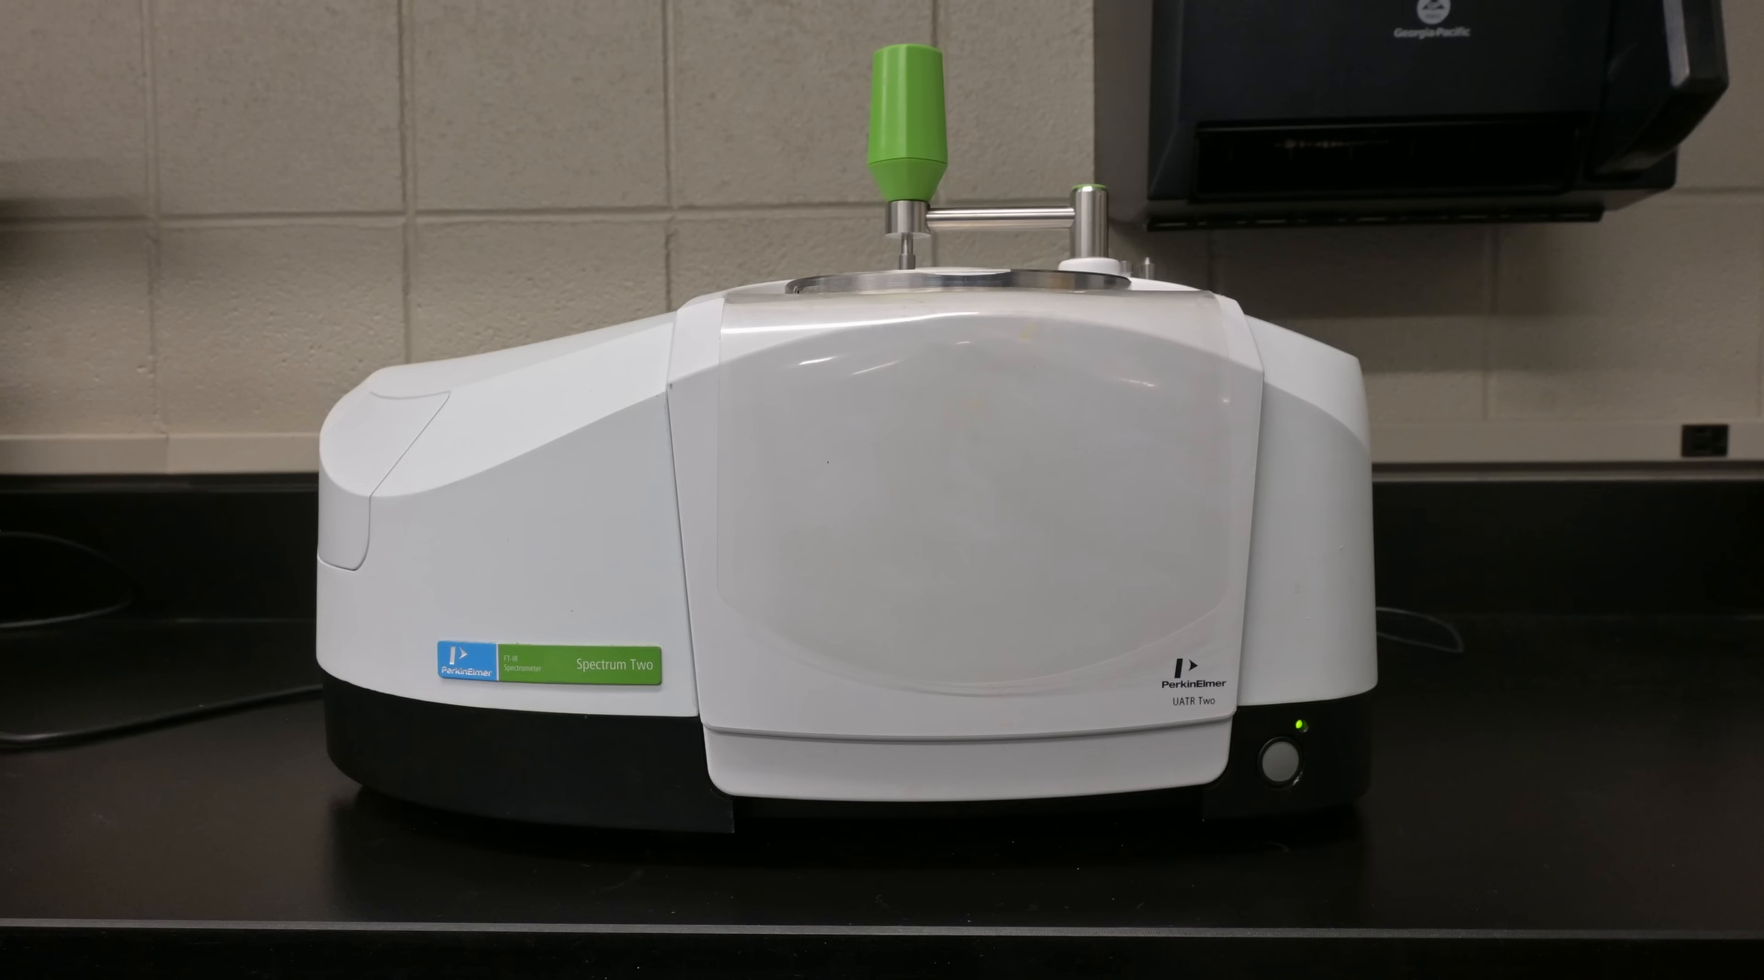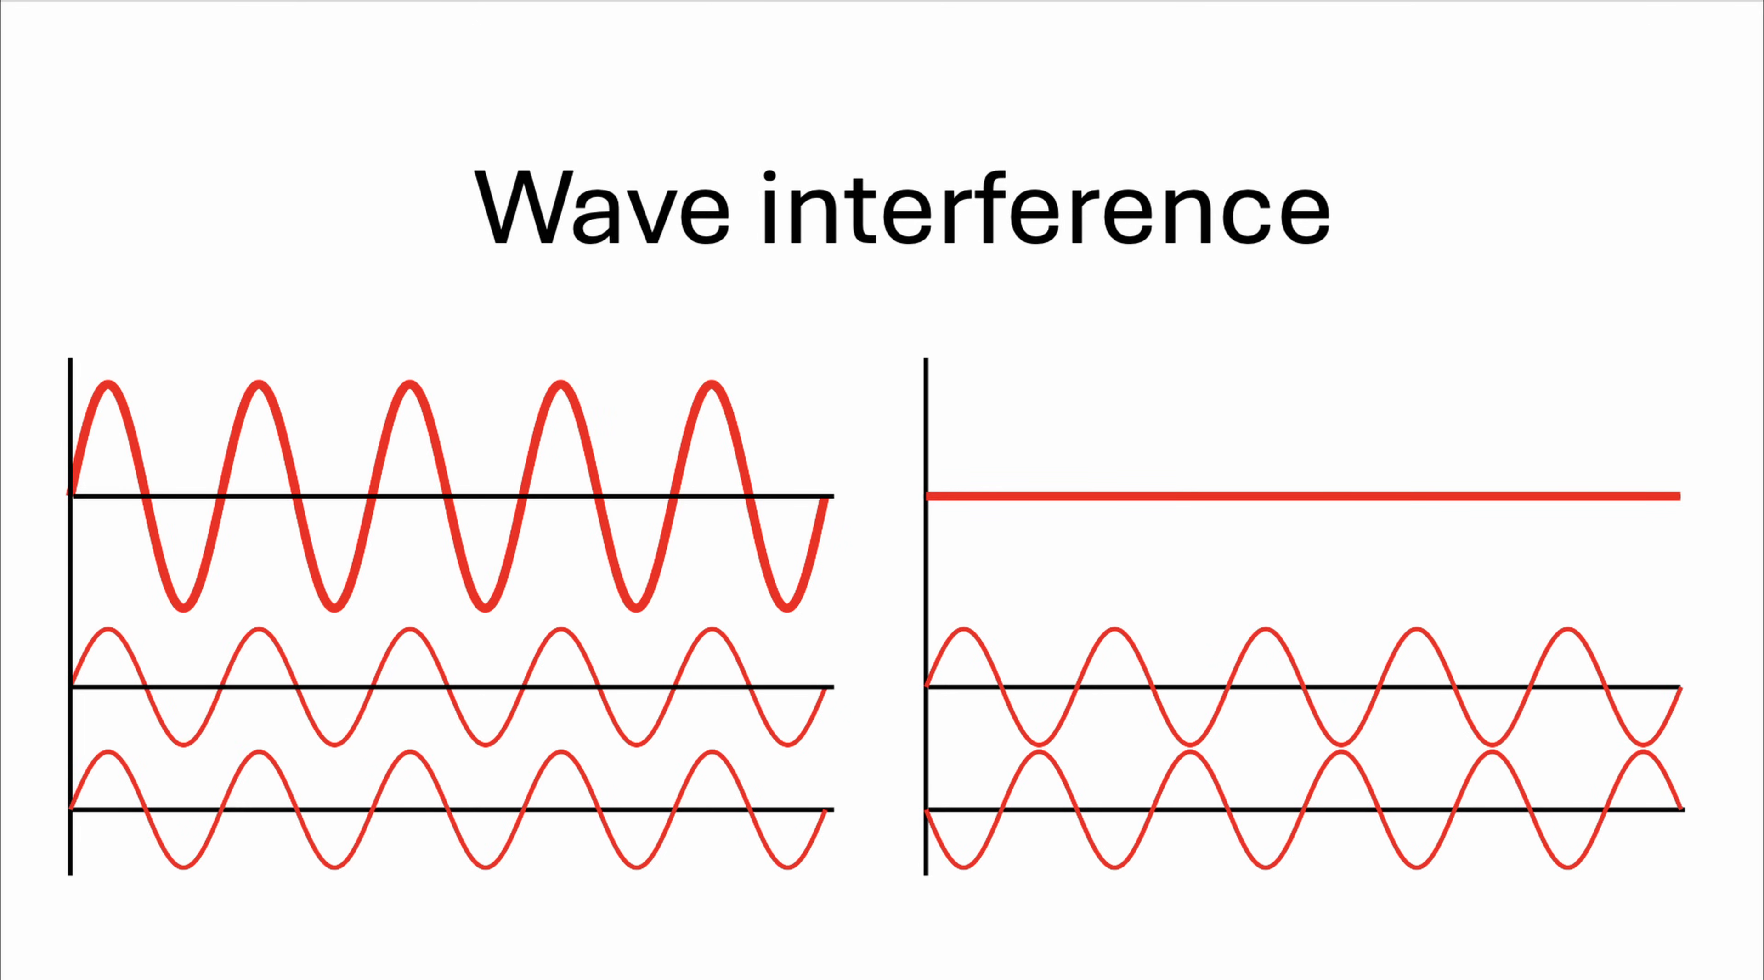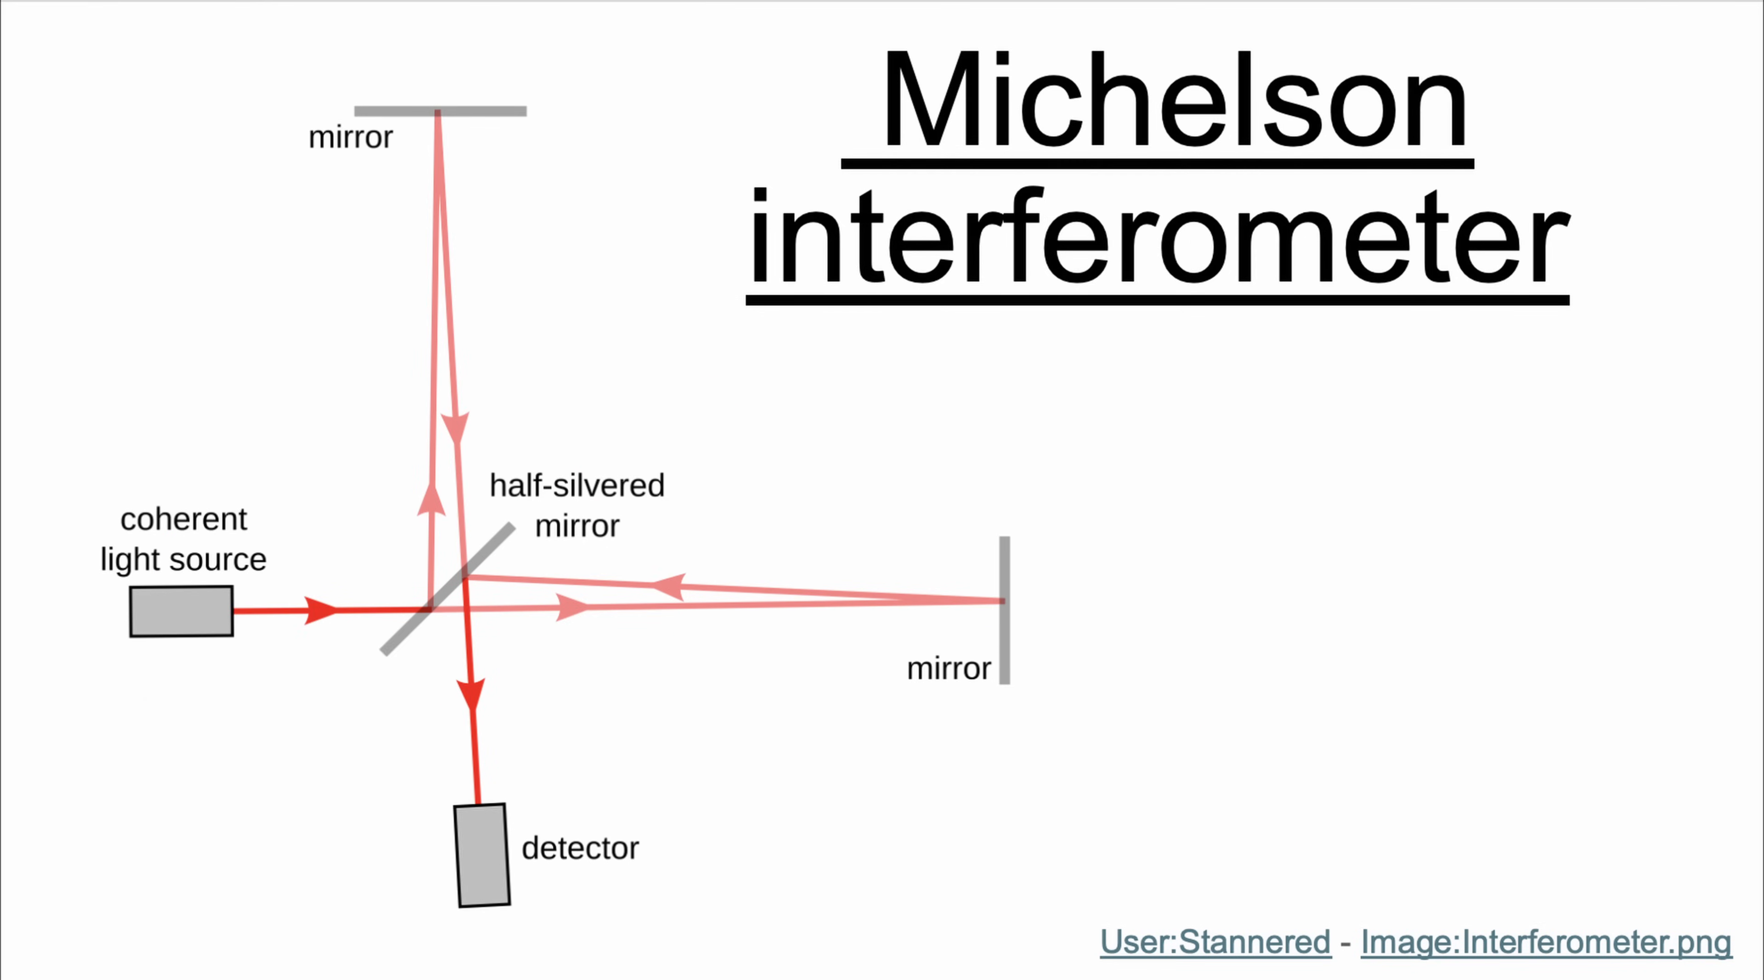The interferometer in an FTIR spectrometer is a device that precisely analyzes IR radiation by creating patterns of interference, essentially how two or more waves combine and overlap. This is crucial because directly measuring infrared absorption across a broad spectrum simultaneously would be challenging. Instead, the interferometer cleverly encodes information about all the wavelengths at once. So how does an interferometer work?